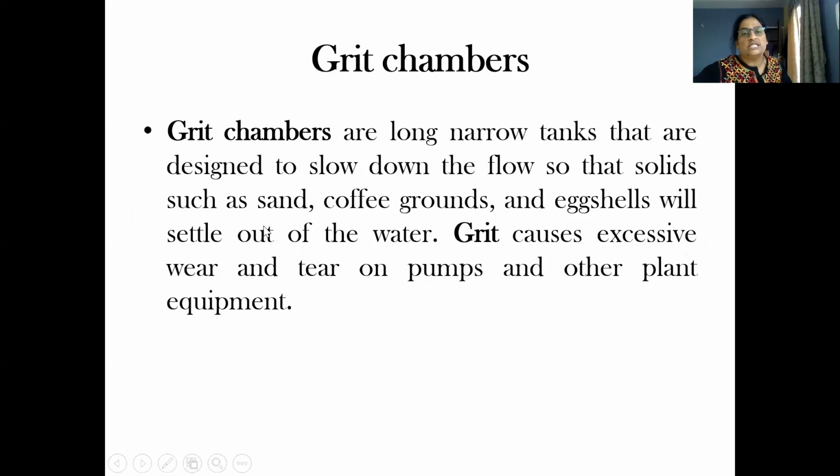So the next unit operation is the grit chamber. What is the function of the grit chamber? Grit chambers are long, narrow tanks that are designed to slow down the flow so that solids such as sand, coffee grounds, eggshells, and pebbles will settle out of the water. Grit causes excessive wear and tear on pumps and other plant equipment. So the grits are usually inorganic materials: eggshells, coffee grounds, sand particles, crushed stones, pebbles, metal.